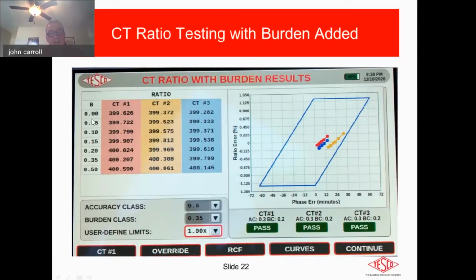And again, it depends on the accuracy levels that your company is deciding you want. Maybe it's up 5%, down 5%, up 10, minus 10, too. It doesn't matter. It just depends on what it is you're specifying. And also check with your classifications that you're checking against. But you can see here, even with added burdens, we're still getting a pretty good accuracy. So this is a pretty good test.